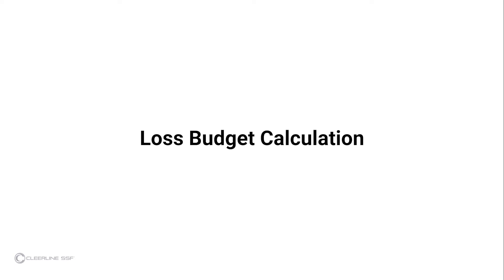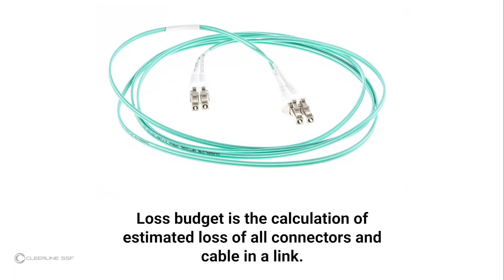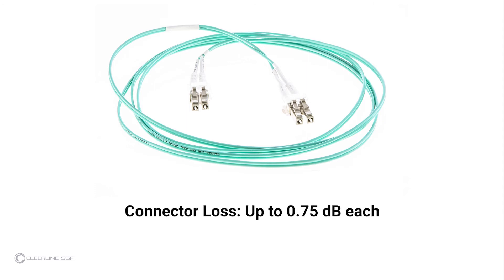Loss budget calculation: Cleerline advocates following established guidelines for insertion loss testing, such as those established by the Fiber Optic Association, and references these FOA standards in both equipment instructions and this video. Loss budget is the calculation of estimated loss of all connectors and cable in a link. Loss budgets can be calculated during design; in testing after installation, the actual loss is compared to the budget to ensure proper installation to industry standard. Each connector under test is allowed up to 0.75 dB per the EIA-TIA 568 standard.